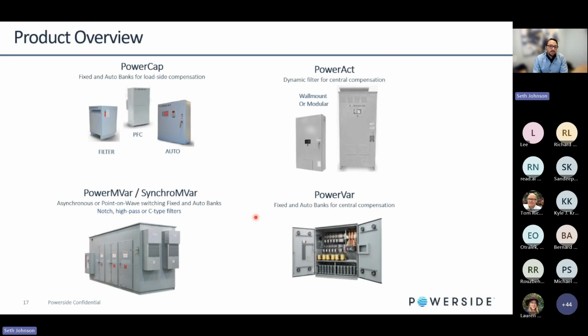Then, of course, the medium voltage product, which we can do both in a Power MVAR product line or a Synchro MVAR, so we can do fast switching or dynamic switching. And we can design these as single tune, multi-tune, high pass or C-type filters. And this, of course, has been a growing market for us as well. We primarily manufacture up to 35 kV class, or I should say 38 kV class, in metal enclosed. If you go above that, typically you're into an open rack configuration.